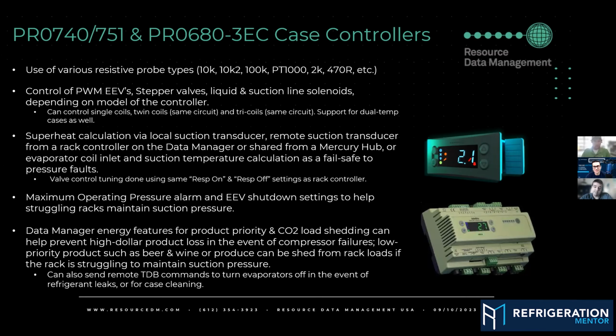That happens not infrequently. Yeah, I know, because the big thing now with CO2 is there are so many more temperature probes and pressure probes, which is great for us after it's set up and commissioned, because now you get so much data, you can troubleshoot so easily. Like if you have a site, Cody could just jump on with you or Chris in a few minutes, and after you learn the trends and how to watch the percentage of the valves opening, it makes life so much easier to troubleshoot compared to back in the day.